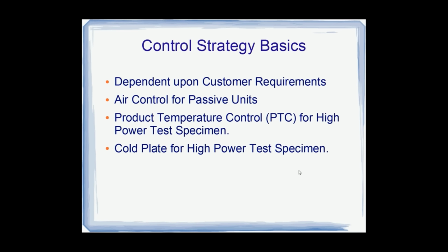You could use air control. This is great because it would eliminate the need to have monitor or response thermocouples on every single unit inside the chamber. This would minimize your setup time and minimize the amount of data you would need to collect. So it would eliminate unnecessary paperwork, and it would speed up setup time by having cold plates for batch testing setups.